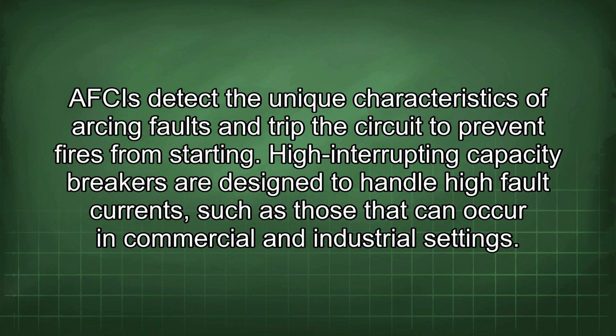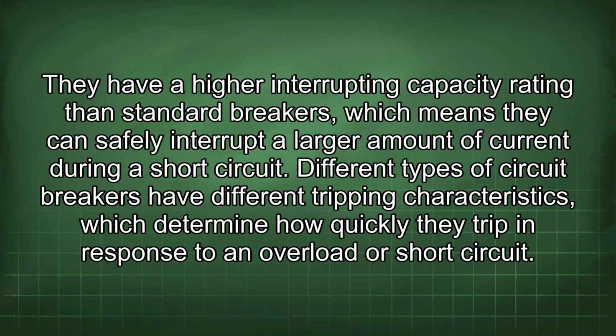High interrupting capacity breakers are designed to handle high fault currents, such as those that occur in commercial and industrial settings. They have a higher interrupting capacity rating than standard breakers, which means they can safely interrupt a larger amount of current during a short circuit.